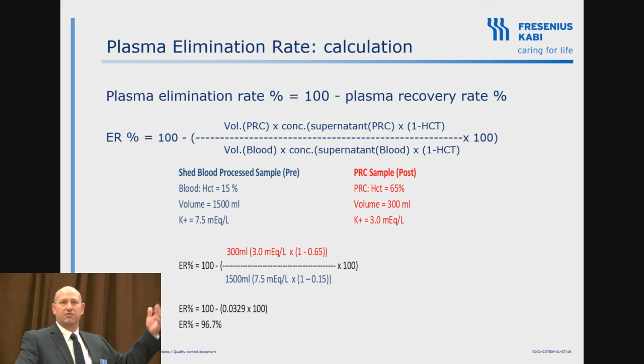So you always have to look at elimination rates. We want to know in QC what our device is doing and make sure it's maintaining the same amount of elimination. So you have to do elimination rates. This is what you send to the FDA to validate your devices and everything. Unfortunately, you have to measure 6 things. You have to measure the blood you're processing and the blood that was processed. I can give you more information on this, but I just wanted to make the point that looking at just an N number tells us very little about what the device did. You have to know what you're starting with and what you ended up with.